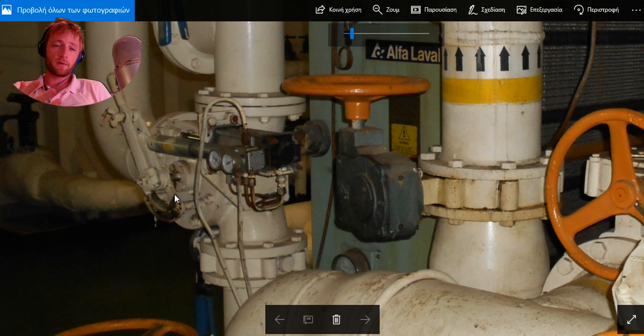and when you are finished with the engine, full away, to see where it's adjusted. If for some reason it goes off, you will need to operate it manually. To operate manually, as you can see, there is a lock device here. You take it out and it disconnects from this actuator. Also, maybe you will need to shut down the air supply here, so this piston can be easily moved. Next, there is a dial gauge here with some points, like a ruler, which indicates how much percent it's open and where the water is sent, bypass or cooler.